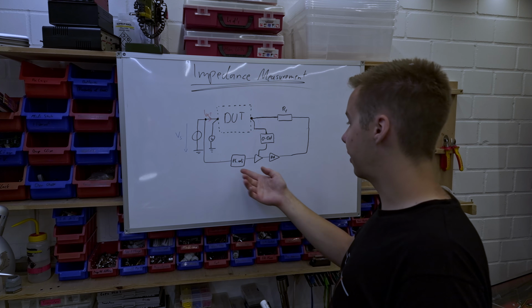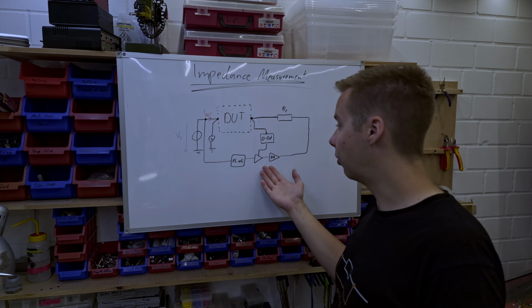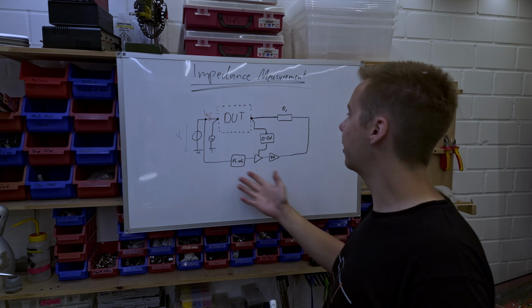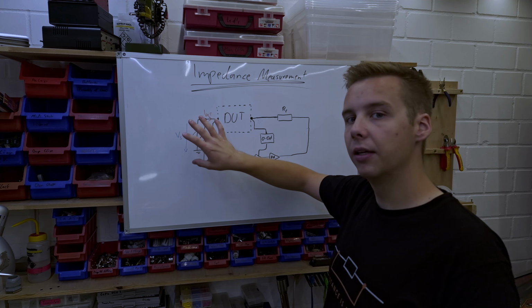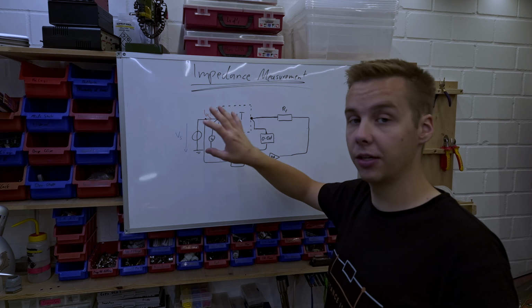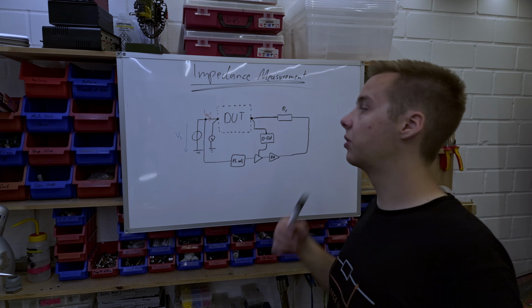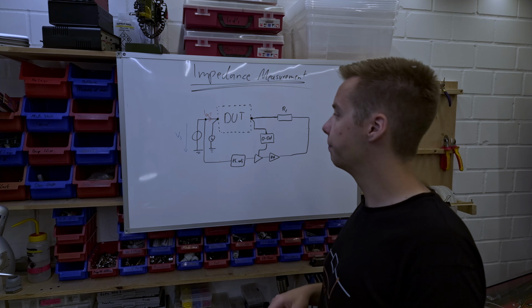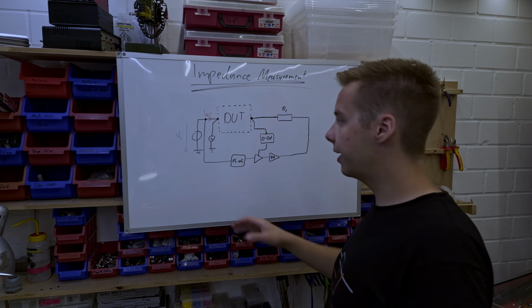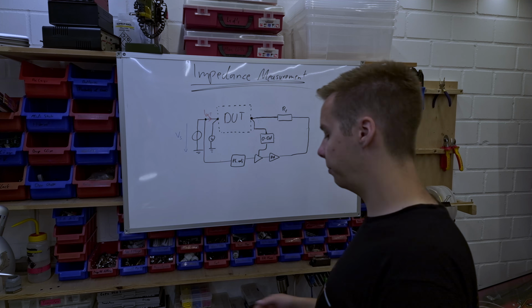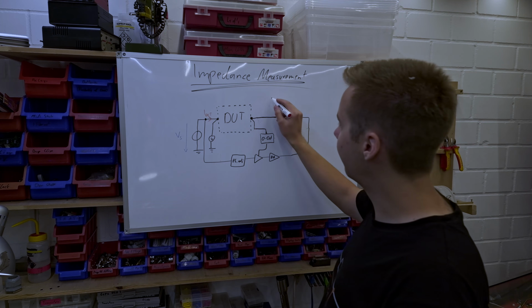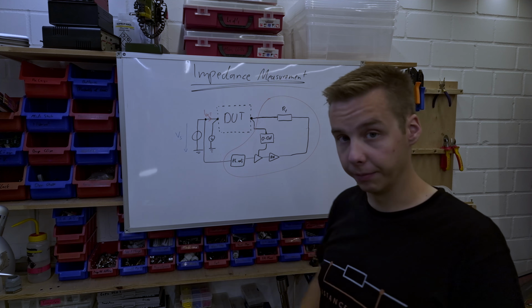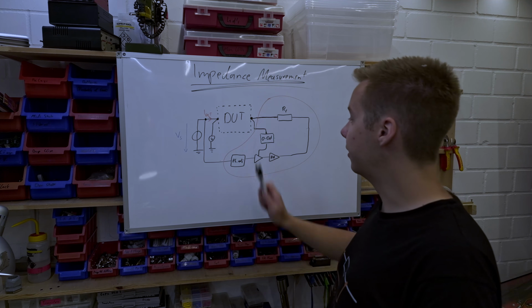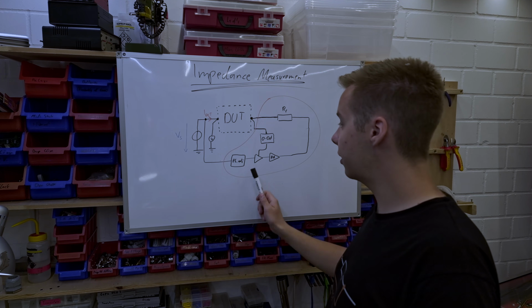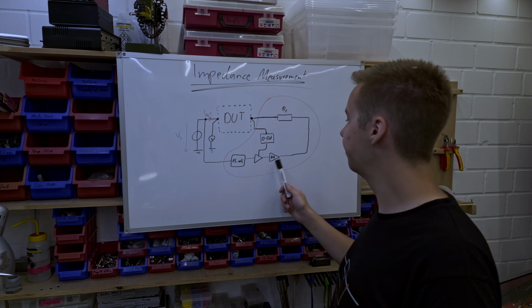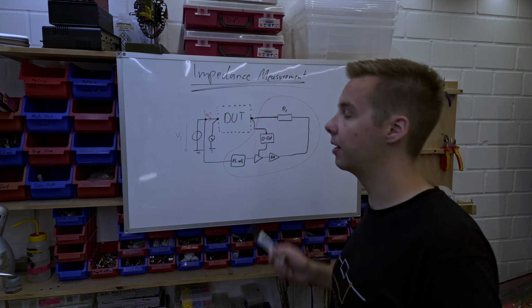Now, in theory, it could also be that, for example, the power amplifier is broken, or the phase adjuster is broken, or any number of these things. It can, however, not be the source side, because in this case, the source side has actually got some supervising circuitry, which makes sure that there's an output, that the output is correct, or at least kind of correct. And an error here would not cause that, so the fault would be anywhere around this section here. So the problem could be in the null detector, it could be in the phase adjust, the controlled amplifier, the power amplifier, or in theory in the resistor as well.